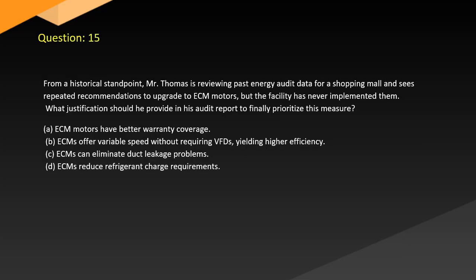Question 15. From a historical standpoint, Mr. Thomas is reviewing past energy audit data for a shopping mall and sees repeated recommendations to upgrade to ECM motors, but the facility has never implemented them. What justification should he provide in his audit report to finally prioritize this measure? A. ECM motors have better warranty coverage. B. ECMs offer variable speed without requiring VFDs, yielding higher efficiency. C. ECMs can eliminate duct leakage problems. D. ECMs reduce refrigerant charge requirements.